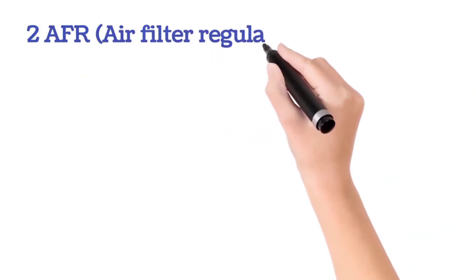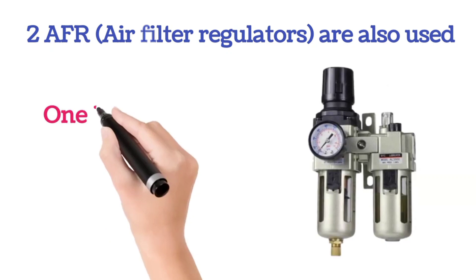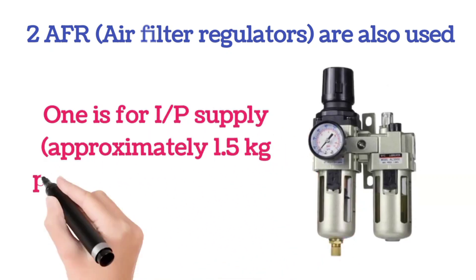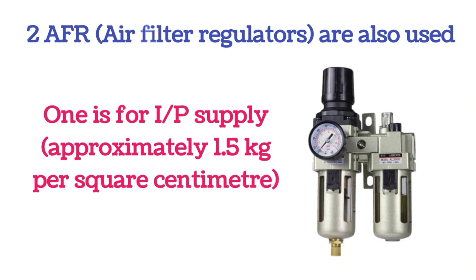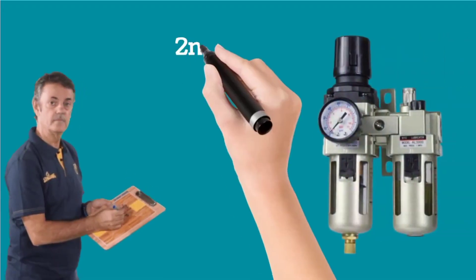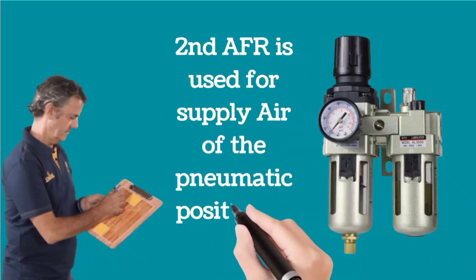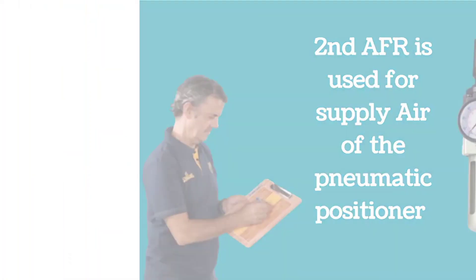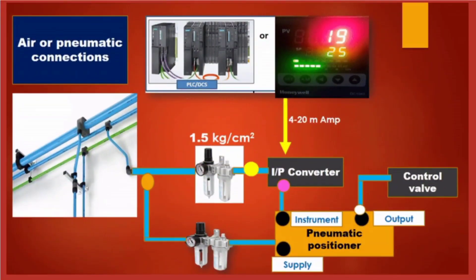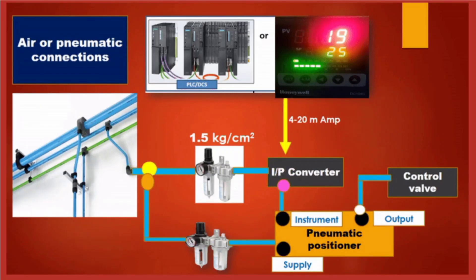Two AFRs, meaning air filter regulators, are used. One AFR is used for the I/P converter supply, which is kept at approximately 1.5 kilograms per square centimetre. The second AFR is used for the pneumatic positioner supply. You can better understand the pneumatic or air connections by this image. Supply air is provided to the air filter regulators for the I/P converter and pneumatic positioner. When the 4 to 20 milliampere signal is fed to the I/P converter, it gives output to the pneumatic positioner, and then the control valve is operated according to the signal.